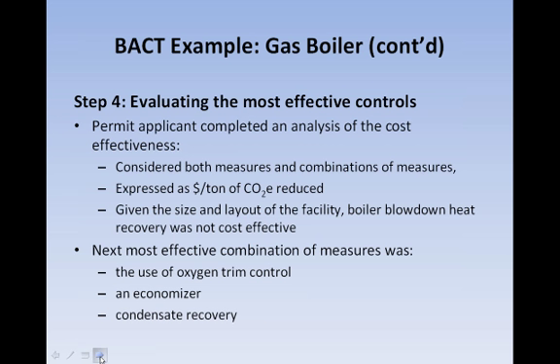And given the size and the layout of this facility, the boiler blowdown heat recovery was not determined to be cost effective. The next most effective combination of measures was the use of oxygen trim control plus the use of an economizer and the condensate recovery. So everything that we had on the most effective combination except for the boiler blowdown heat recovery.